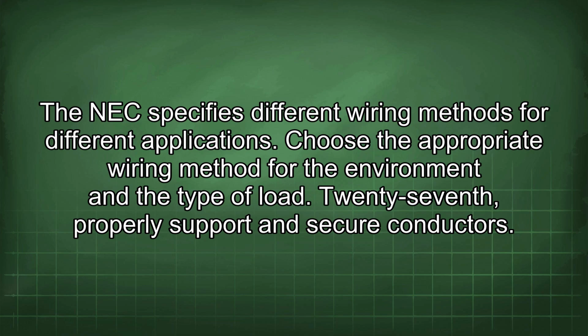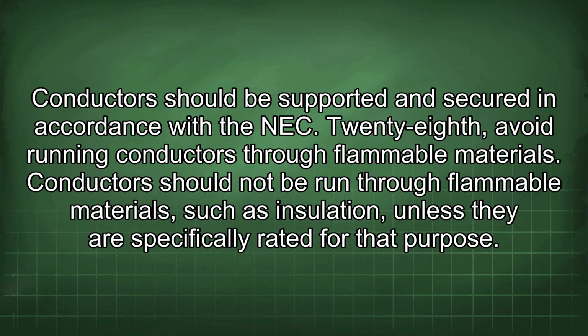27th, properly support and secure conductors. Conductors should be supported and secured in accordance with the NEC. 28th, avoid running conductors through flammable materials. Conductors should not be run through flammable materials such as insulation unless they are specifically rated for that purpose.